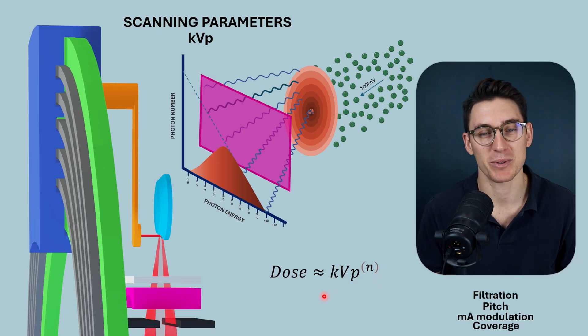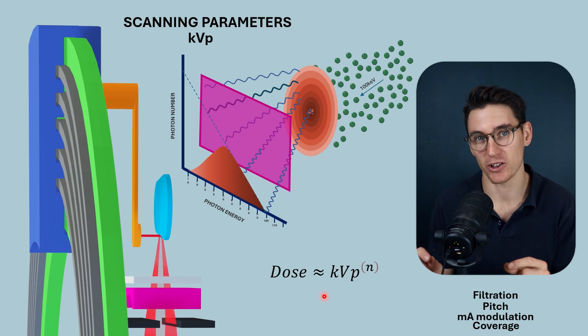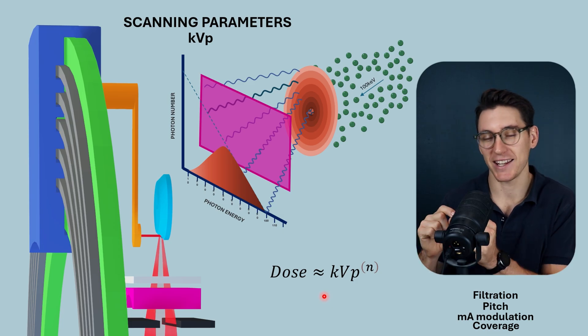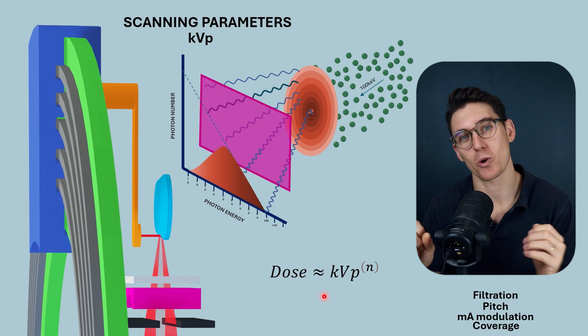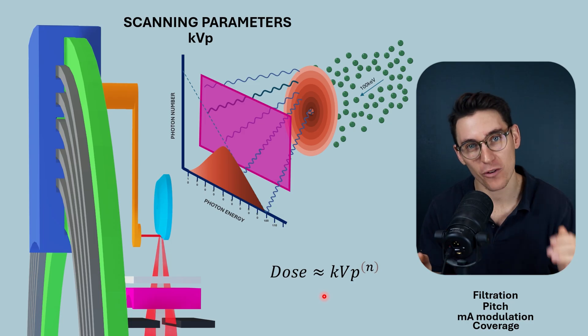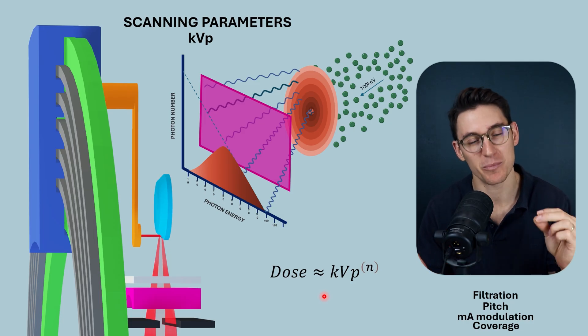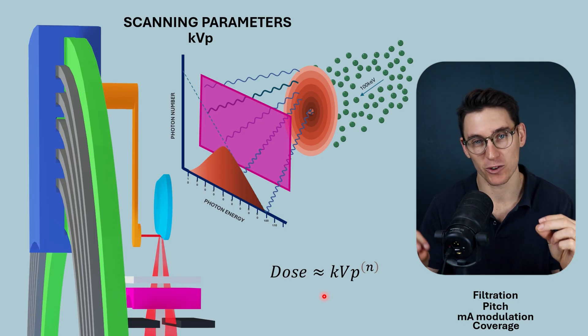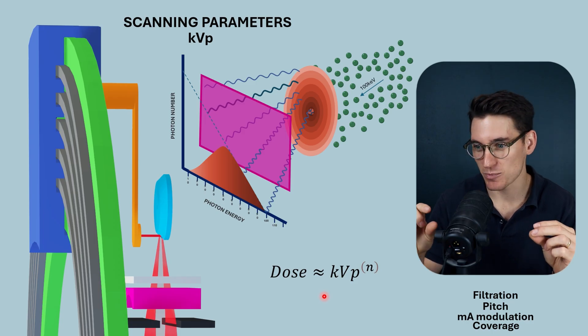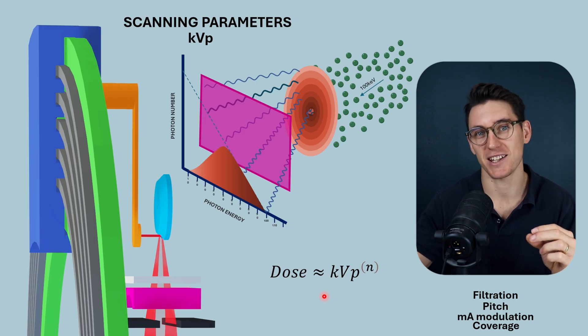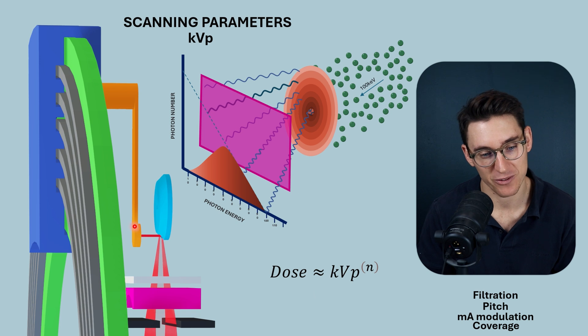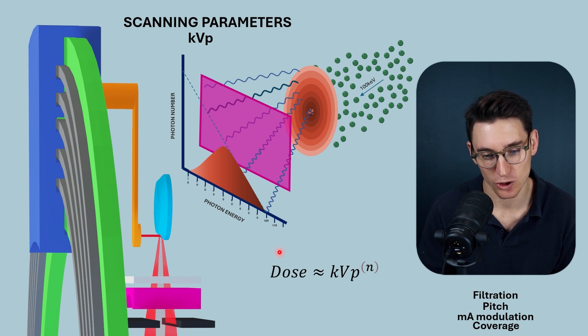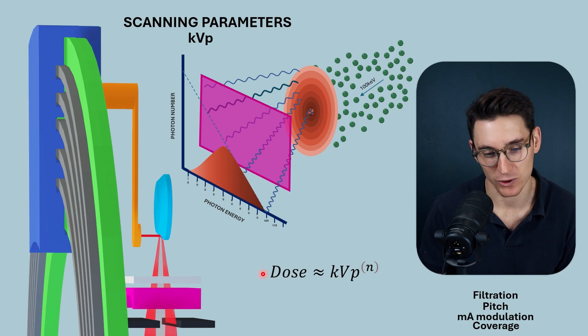You may remember the 15% rule from radiography, where increasing the KVP by just 15% would require a halving of the milliamperes of filament current in order to keep the dose the same. A small 15% increase required a halving of the filament current, which just shows you how much of a role KVP has to play in dose.